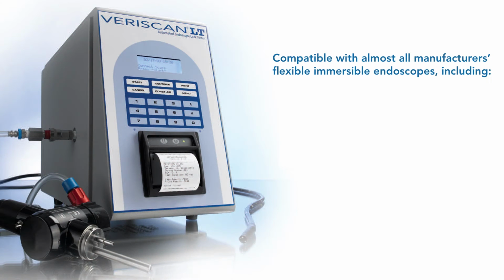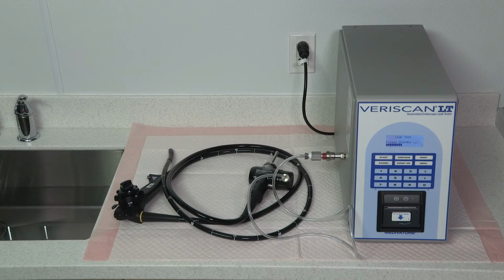The VERISCAN Leak Tester is compatible with almost all manufacturers' flexible immersible endoscopes, including Olympus, Pentax, Fujifilm, and Karl Storz endoscopes. Always follow the endoscope's manufacturer's instructions and established professional guidelines to properly leak test and clean an endoscope. An effective endoscope pre-cleaning process and leak test are essential steps prior to endoscope disinfection, and the VERISCAN Leak Tester is used to complete the leak test phase.